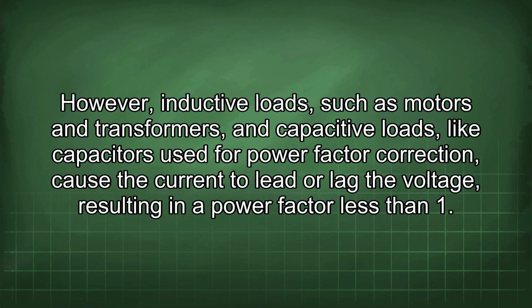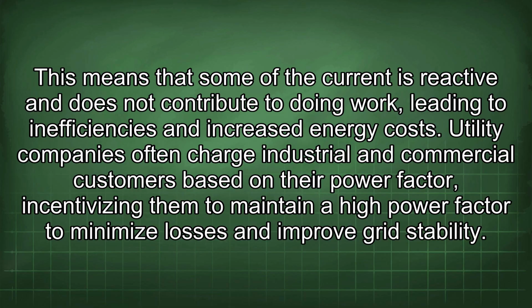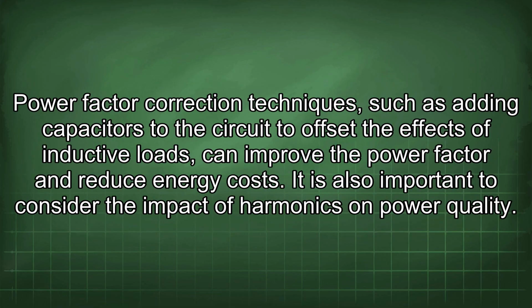However, inductive loads, such as motors and transformers, and capacitive loads, like capacitors used for power factor correction, cause current to lead or lag the voltage, resulting in a power factor less than 1. This means that some of the current is reactive and does not contribute to doing work, leading to inefficiencies and increased energy costs. Utility companies often charge industrial and commercial customers based on their power factor, incentivizing them to maintain a high power factor to minimize losses and improve grid stability. Power factor correction techniques, such as adding capacitors to the circuit to offset the effects of inductive loads, can improve the power factor and reduce energy costs.